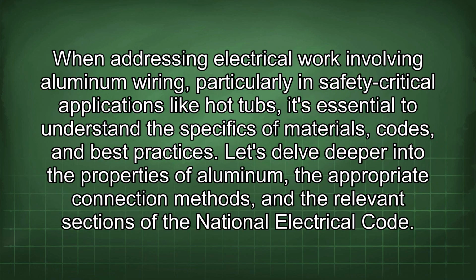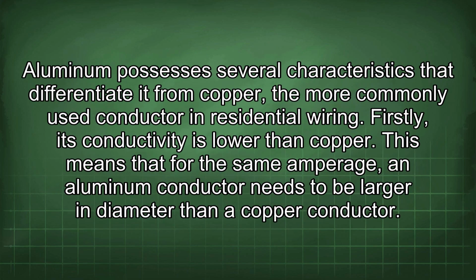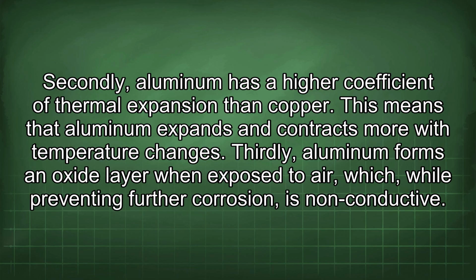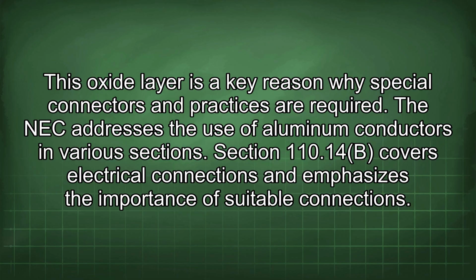When addressing electrical work involving aluminum wiring, particularly in safety-critical applications like hot tubs, it's essential to understand the specifics of materials, codes, and best practices. Let's delve deeper into the properties of aluminum, the appropriate connection methods, and the relevant sections of the National Electrical Code. Aluminum possesses several characteristics that differentiate it from copper, the more commonly used conductor in residential wiring. Firstly, its conductivity is lower than copper. This means that for the same amperage, an aluminum conductor needs to be larger in diameter than a copper conductor. Secondly, aluminum has a higher coefficient of thermal expansion than copper. This means that aluminum expands and contracts more with temperature changes. Thirdly, aluminum forms an oxide layer when exposed to air, which, while preventing further corrosion, is non-conductive. This oxide layer is a key reason why special connectors and practices are required.